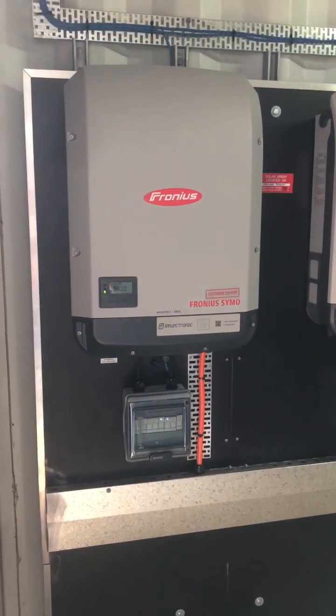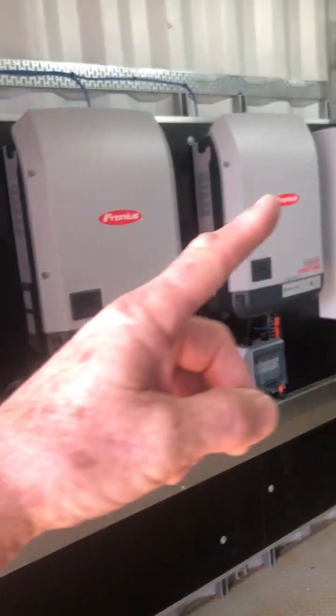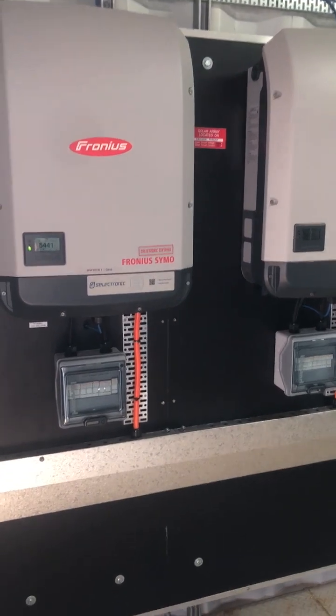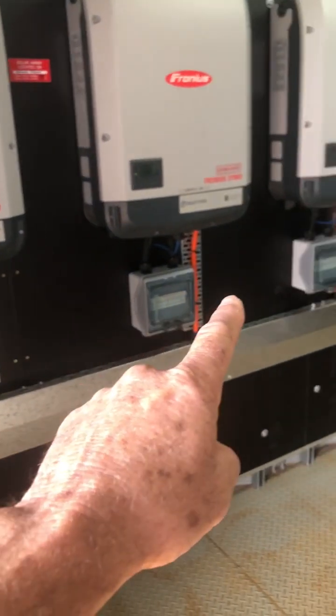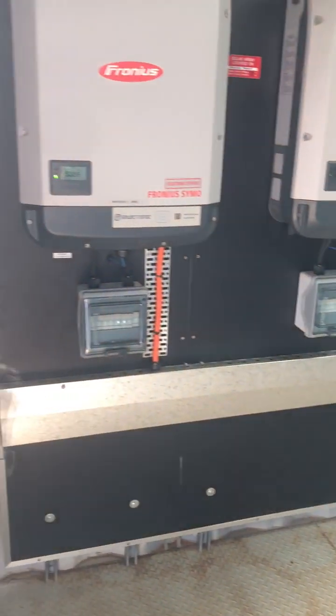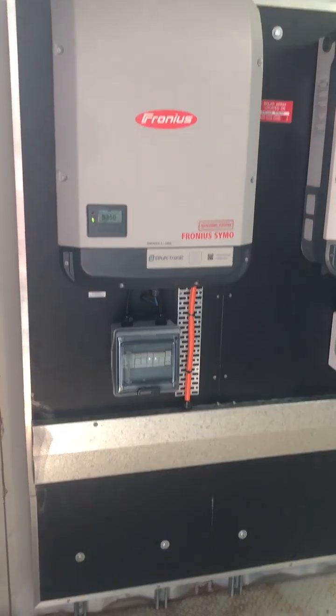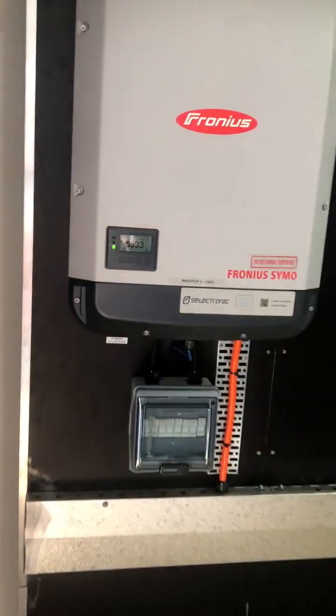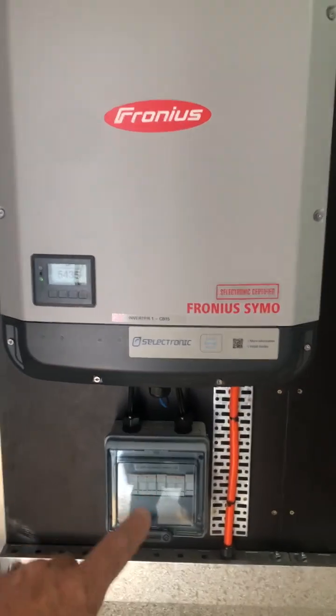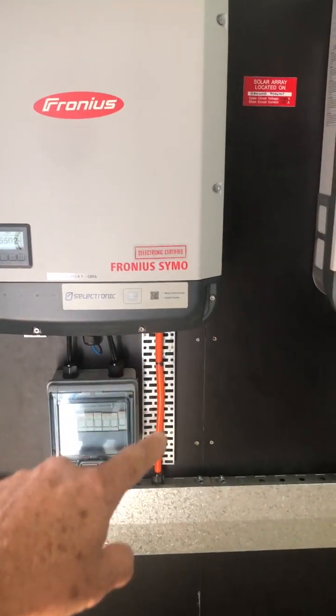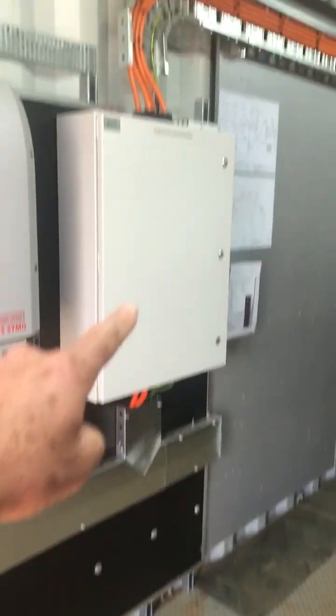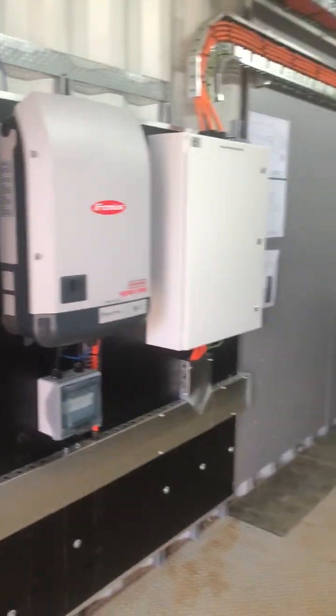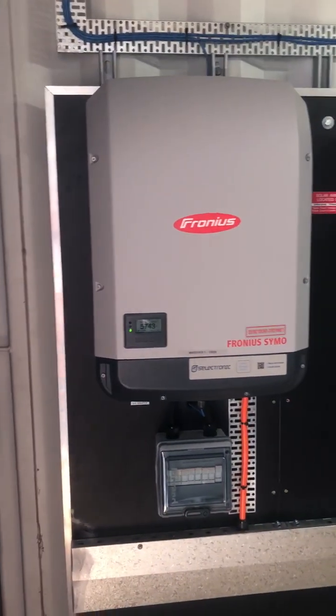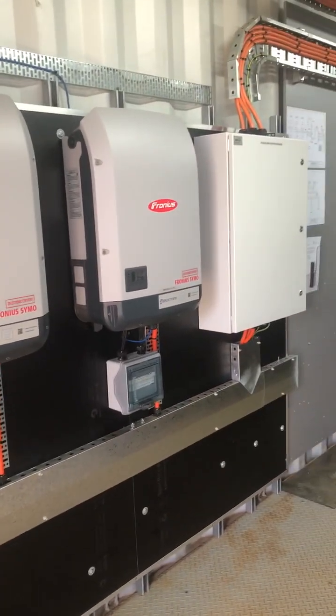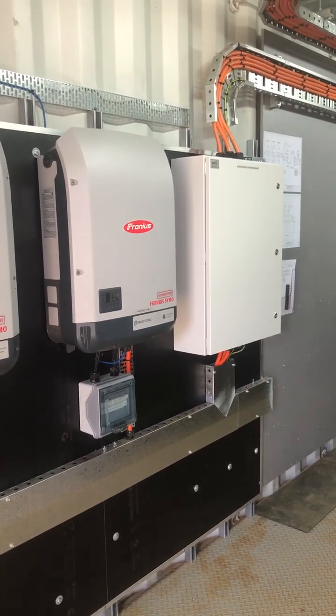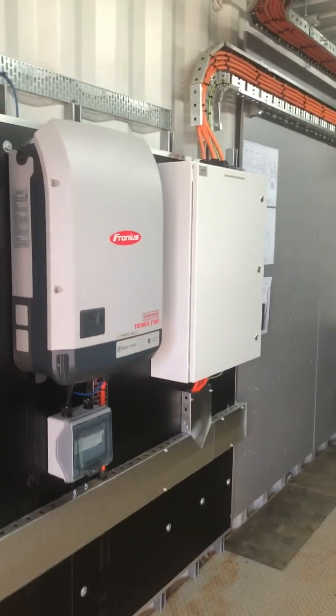On this side of the wall, you'll see the MPPT inverters, and the string cables which you saw outside. They all come into these string fuse boxes. Each string has a fuse on it, and if you've been designing systems, you'll understand why. Then the DC side comes up into the inverter. The inverter has AC cables that go out and up into the PV distribution board. So that's the MPPT side, and this is where we're getting our renewable energy resource coming into the system and providing the energy to charge the batteries.